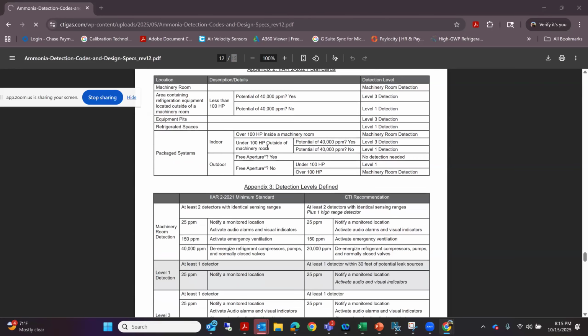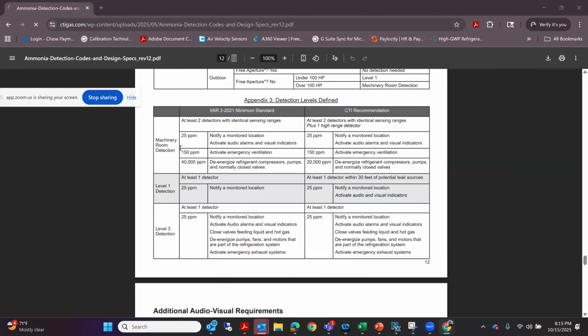we've come in here and we've searched by location of all these different sensors throughout the refrigerated spaces and package systems and machinery rooms and equipment pits and what they call out for level 1 and level 3 detection. And so we went in and defined, well, what are we supposed to be doing, right? And so we broke it out again. What is level 1? What is level 3 doing? And what is the machinery rooms doing? And this is the output functions that you would be seeing from the standard. And then you would be seeing this from what CTI recommends. So this is kind of what the manufacturer's recommending, right?